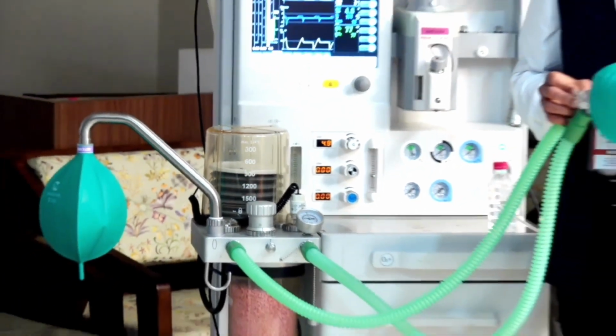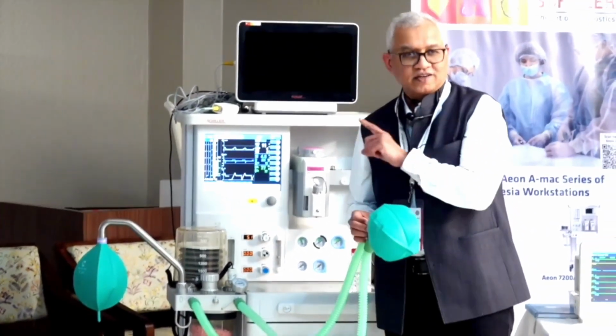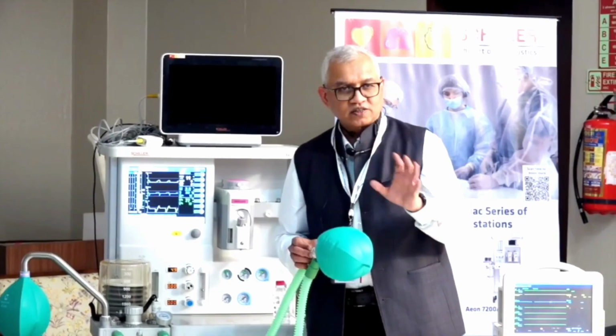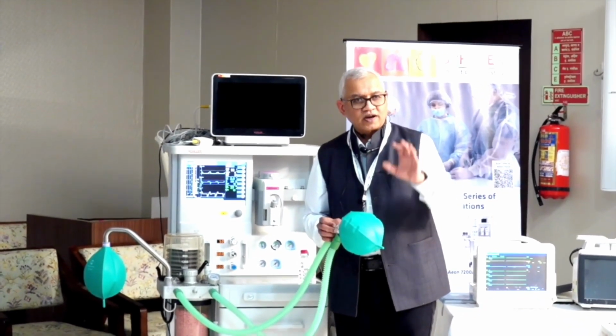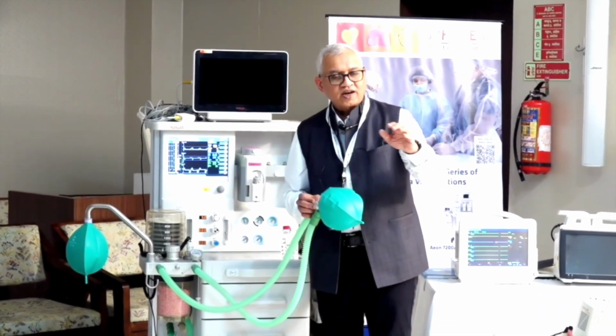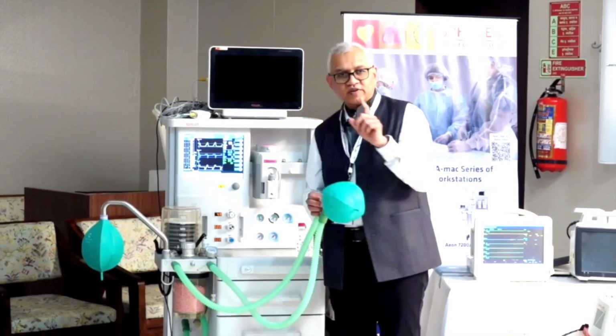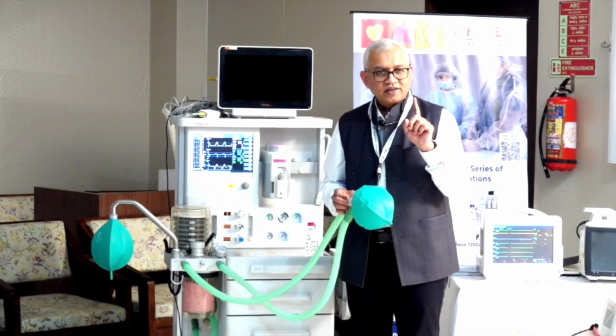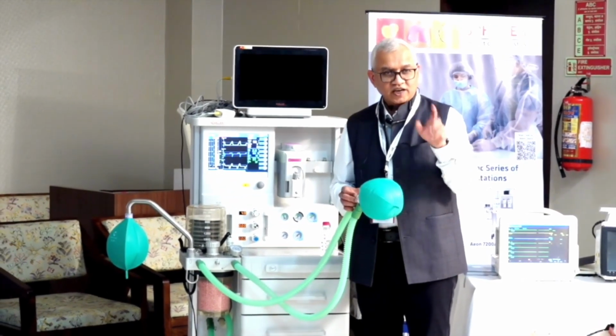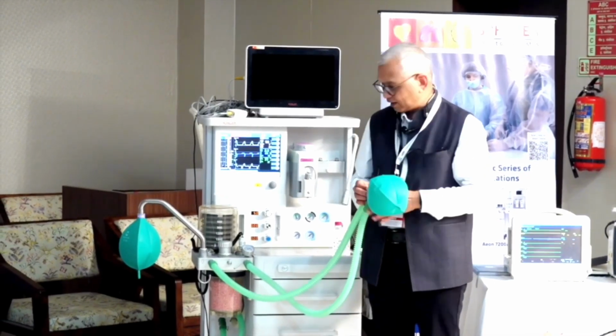So you can quantify this leak. If there is a small leak in your system, by gradually reducing your flow, and seeing at what flow this stops achieving the proper height, is a way of checking it if you do not have a proper pre-test. Okay.